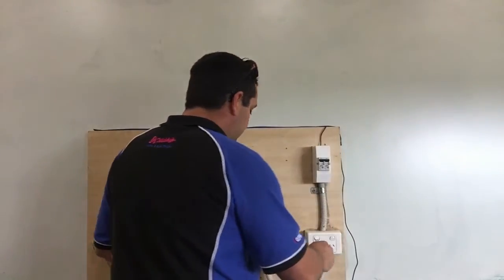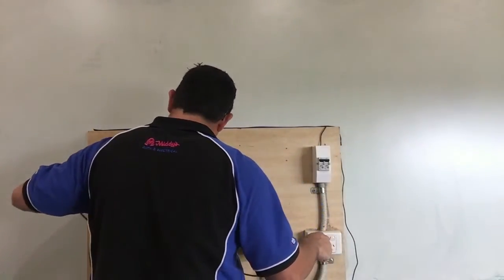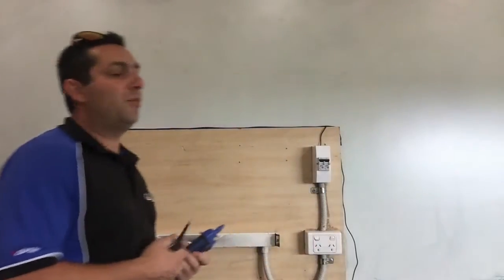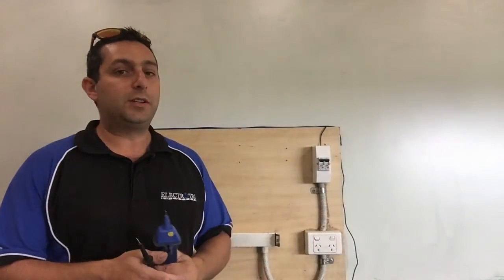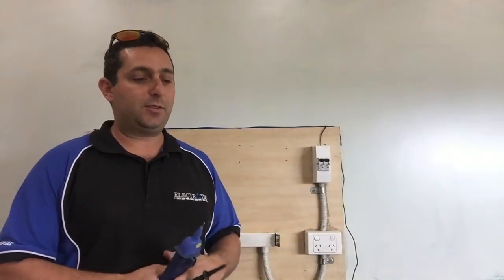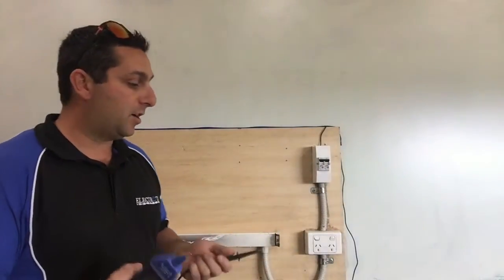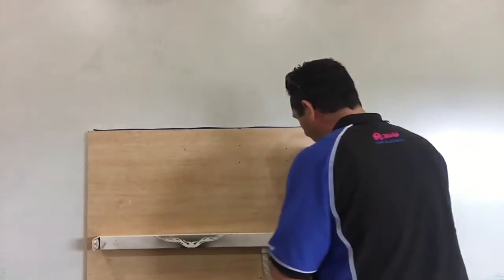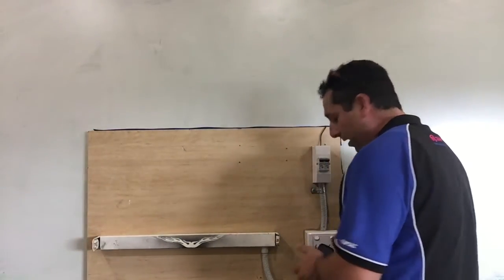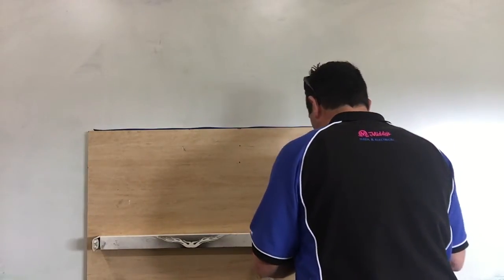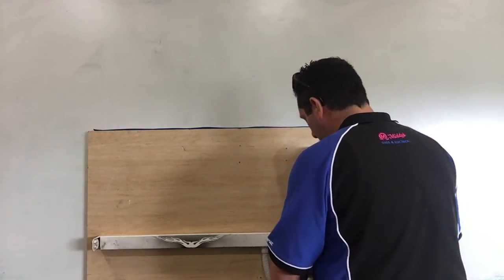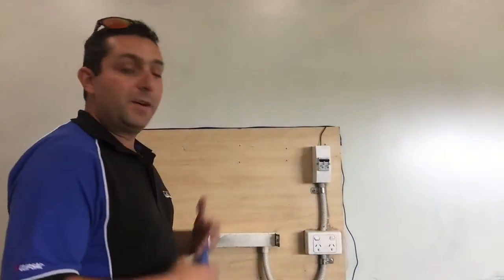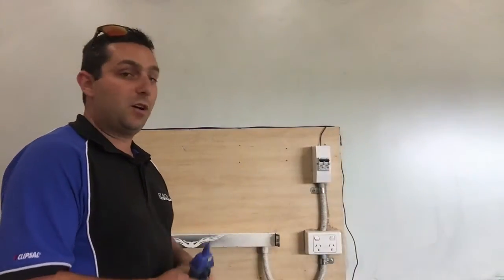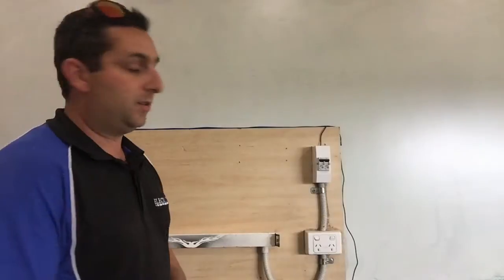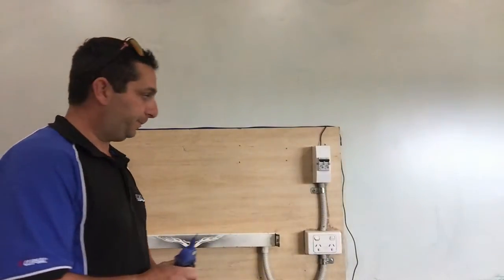Okay, so I'm going to say this is my known earth, and you'll test to your frame in 3 spots. Now, although my tester just showed that there's no voltage present, we can't be 100% certain that my tester is working or functioning properly. So we will need to test our tester on a known live source. So you'll find somewhere a known live source where we can go, we have active, neutral, active earth, neutral earth, and establish that yes, my tester is working fine. So I've tested the frame, there's no stray voltages, I've tested my tester, I know that's right. So in theory, we should be right to touch this and start to work on our appliance.